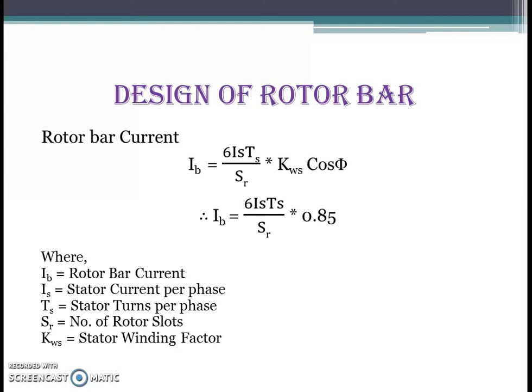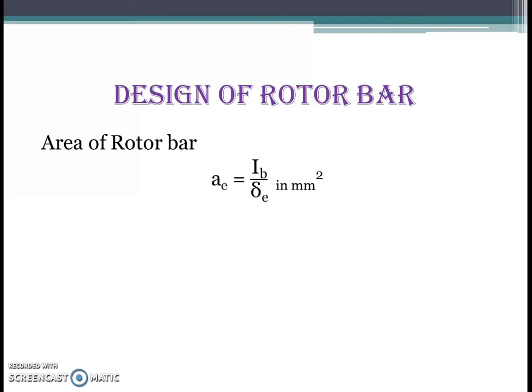Once the rotor bar current is available, it is very easy to calculate the area of the rotor bar. The area equals the current divided by the current density, giving us the cross-sectional area of the rotor bar.